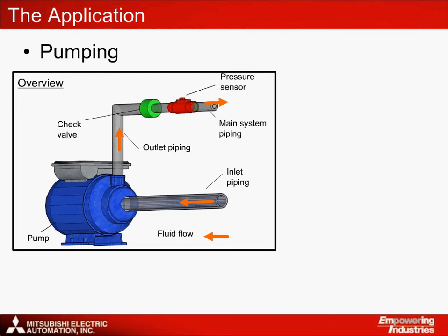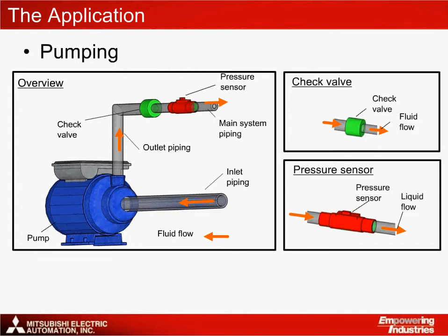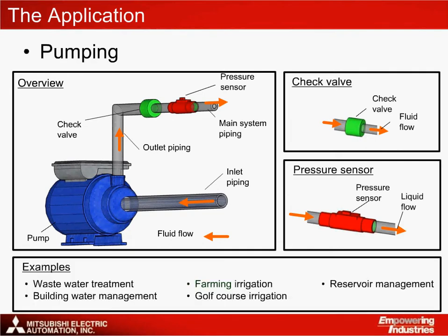The system consists of three main parts: the pump, the check valve, and the pressure sensor. The fluid is provided from the supply. The pump then pressurizes the fluid, after which the outlet piping is used to pass the fluid to the delivery point. The check valve operates as a one-way valve. Once the pressure has reached the threshold within the main system piping, the inverter is able to stop pumping as the one-way valve stops any pressure loss caused by backflow. The pressure sensor provides feedback to the inverter regarding the pressure of the main piping. This feedback signal allows the inverter to determine when pumping is necessary within the system.